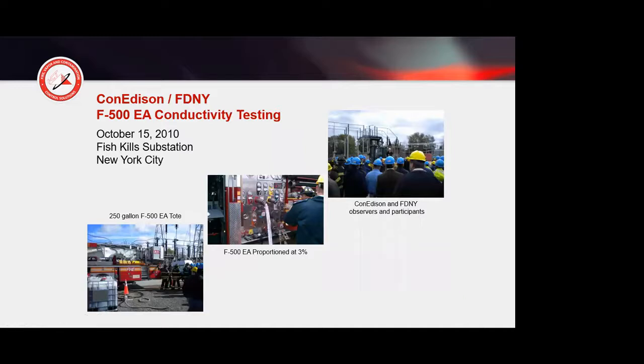But what happened was, because of the performance, they came back and said, since this agent's so effective, let's test it to see if we can actually spray this agent onto an energized transformer, or at least onto a de-energized transformer in an energized environment. Because transformers are at power plants, and while one of them may be on fire and de-energized, all the equipment around you is still energized. So we embarked with FDNY and Con Edison to do some leakage current F500EA conductivity studies. These are just some pictures from the fire ground.